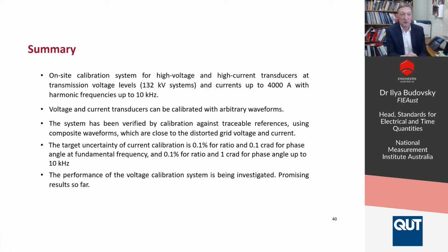So in summary, we are developing an on-site calibration system for high voltage and high current transducers for transmission level voltages and currents. Very importantly, we will calibrate these current and voltage measuring devices with arbitrary waveforms. We can come on site and generate the fundamental and the harmonic of any kind that would represent what can be present in real situations on real power lines in the real grid. Our target uncertainty is 0.1% for the ratio and 0.1 centiradian for phase. We are well ahead of that for current, and we are working to achieve that, and hopefully much better than that in voltage.